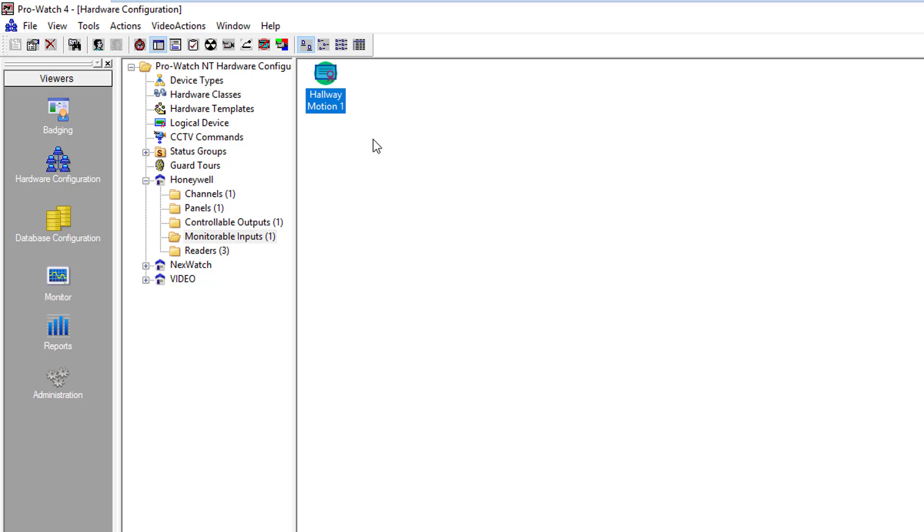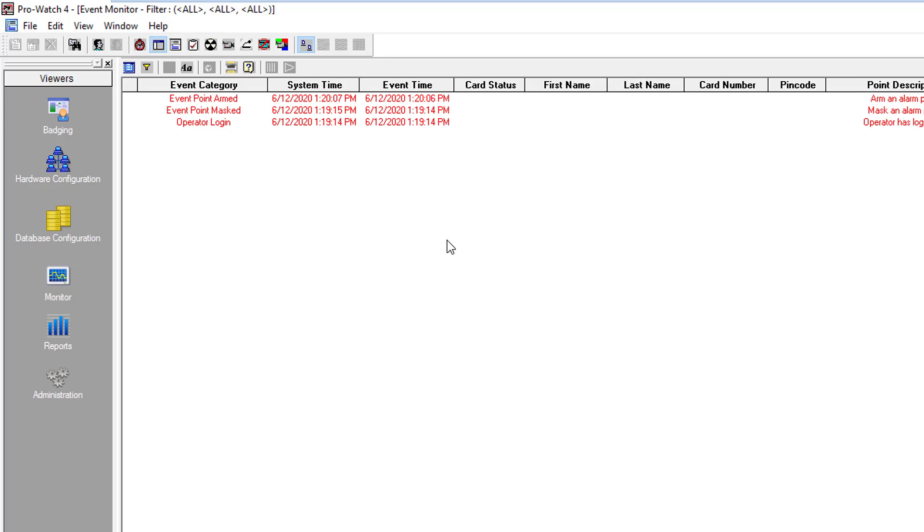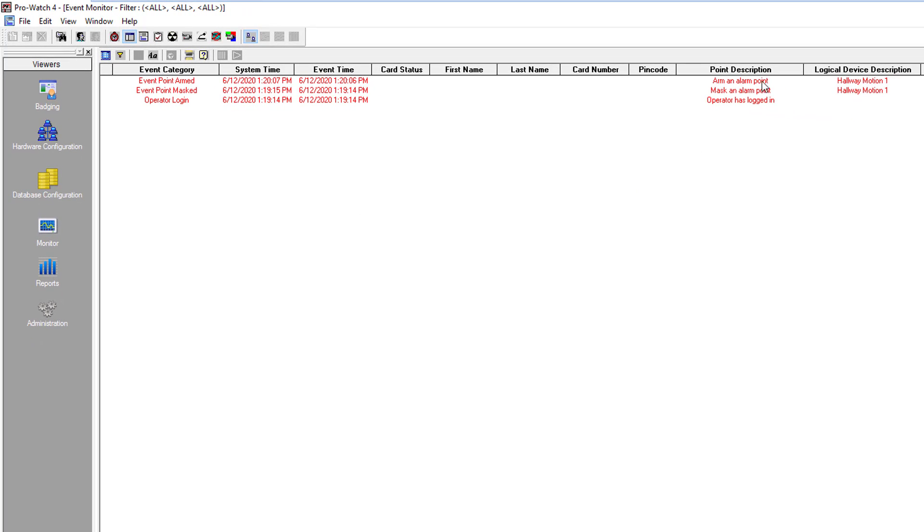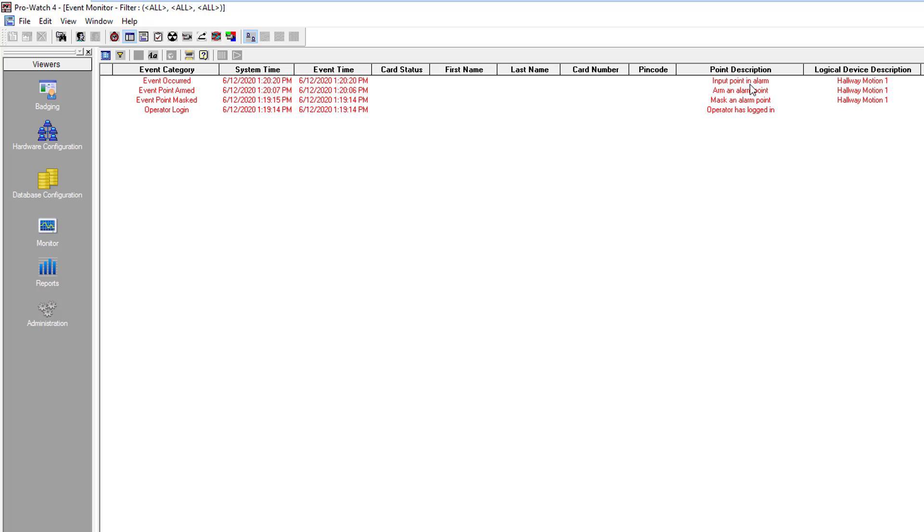Now the mask is off and the input should be working correctly. Go back over to toggle events. And as you can see now it says arm the alarm point. So now it is active. So when I push it you can now see that it did go into alarm and return to normal as is expected.